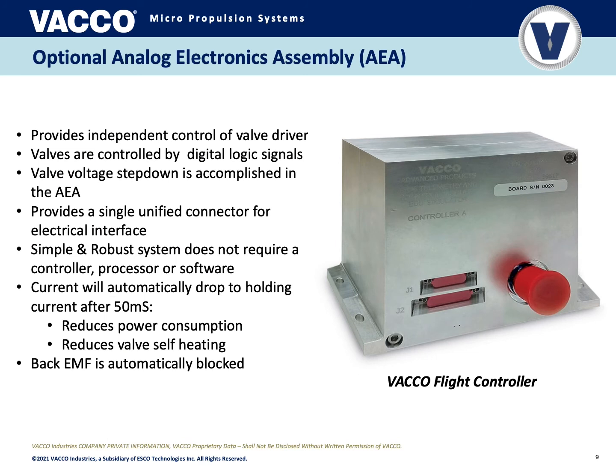The optional analog electronics assembly, or AEA, is just that. It's an option. The standard system is provided with no controller whatsoever. The customer directly controls the valves and reads the pressure transducer. In this case, the analog assembly is a collection of valve drivers that can be provided for the convenience of our customers, so that instead of directly applying 28 volts to the valves, you would be providing a logic level signal that will drive the valve.